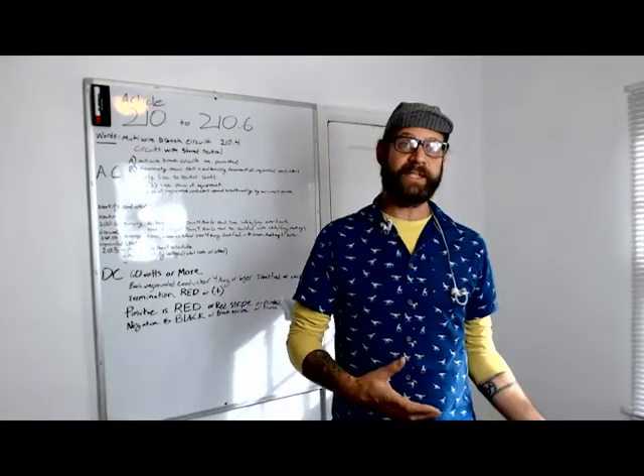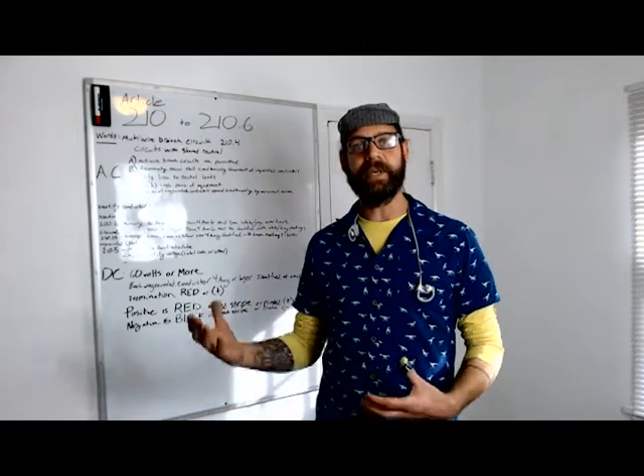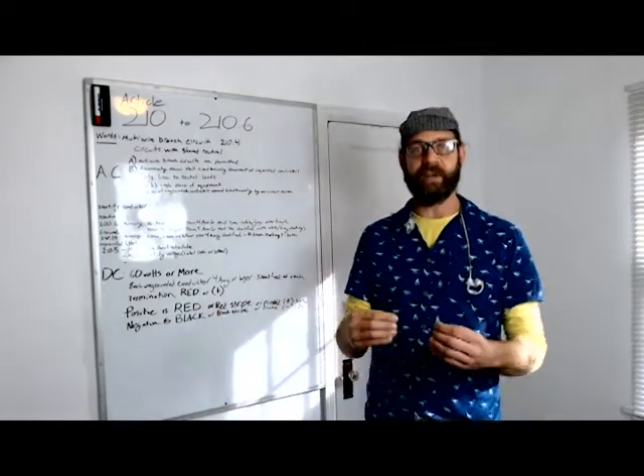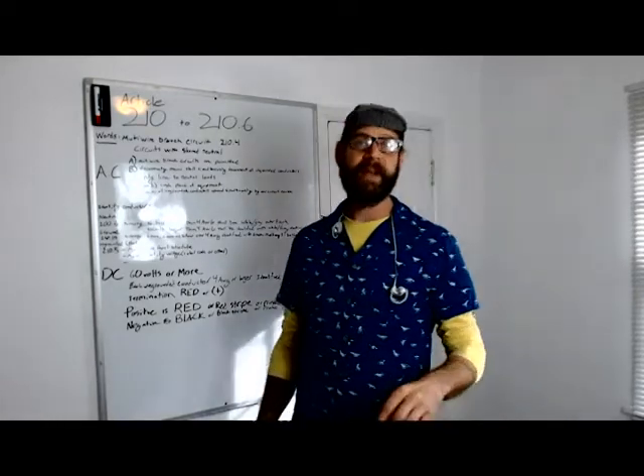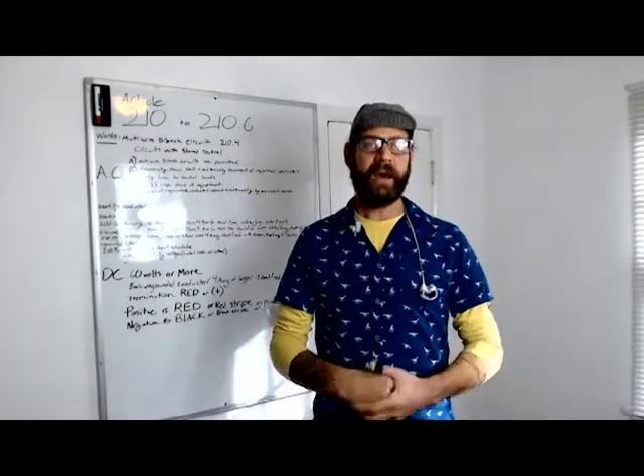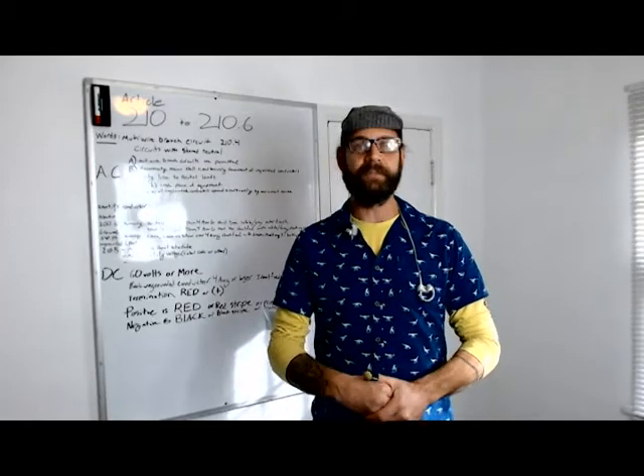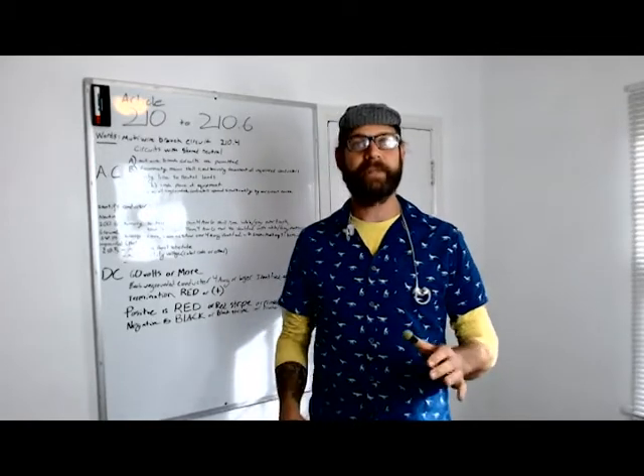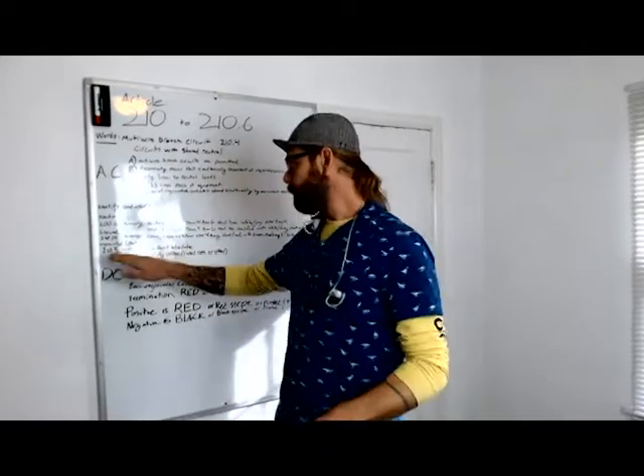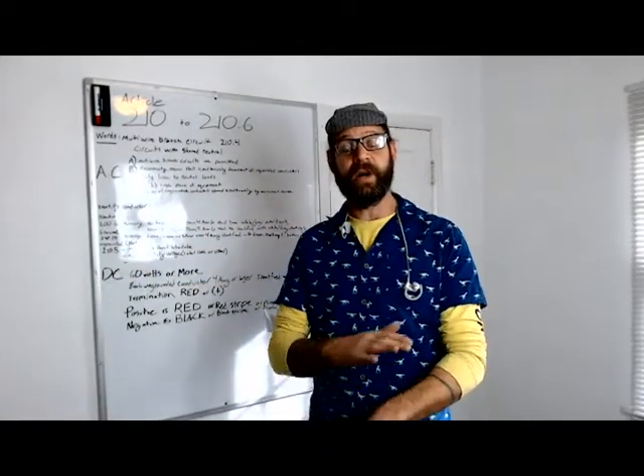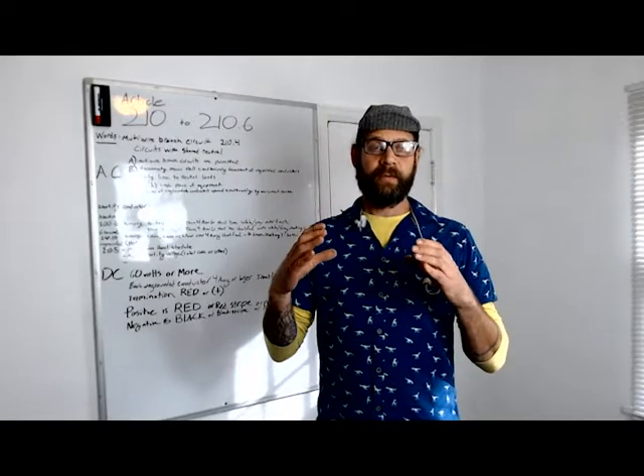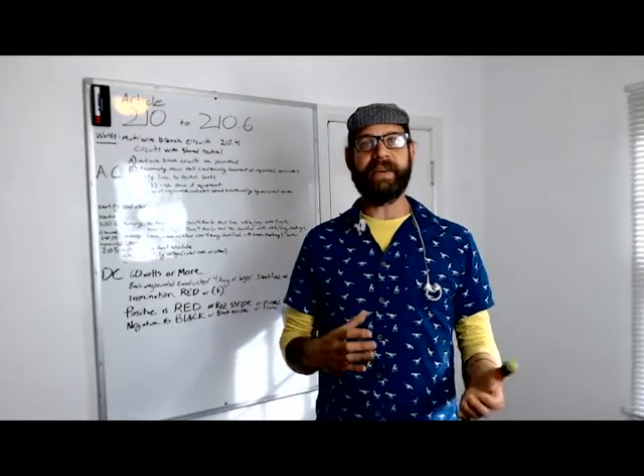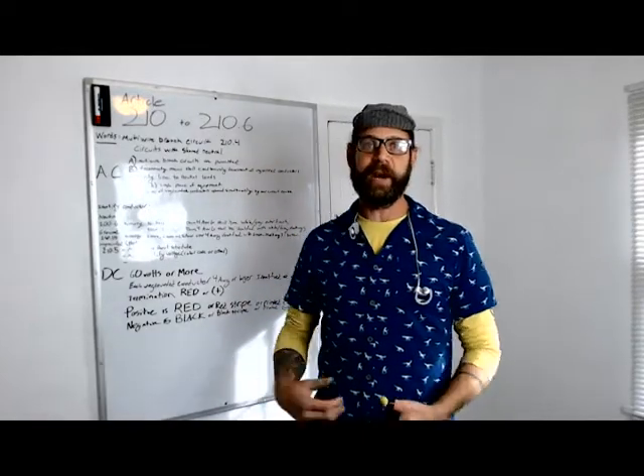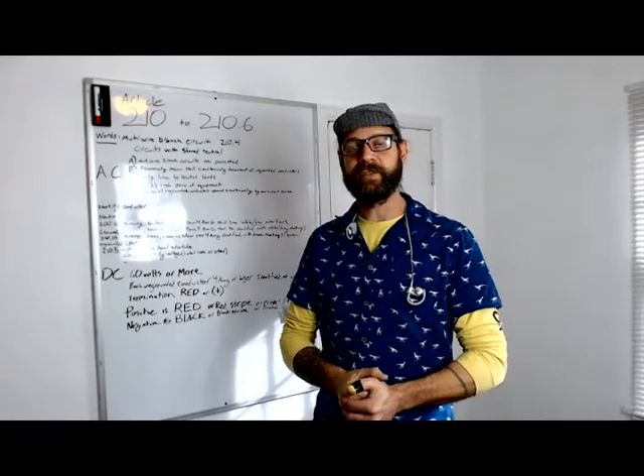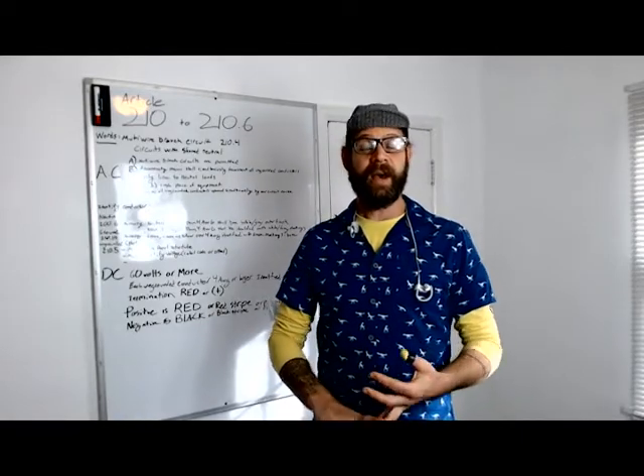And likewise, if it's over 4 AWG, it's going to be identified at all of its termination points and all of its splice points with green marking. And most of the time, that's going to be green electrical tape. It can also be shrink tubing, although in practice, green electrical tape. There you go. This is the portion of the code where it identifies how you should identify your hot conductors. So the ungrounded, the hot conductors cannot be white and they cannot be green.